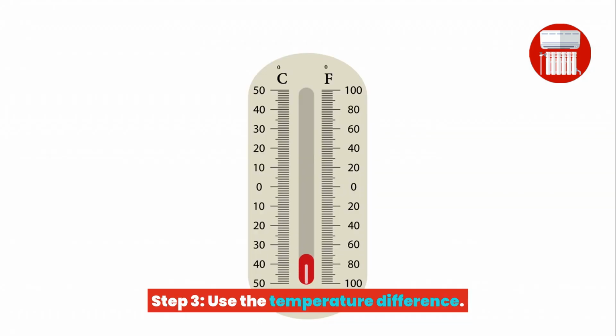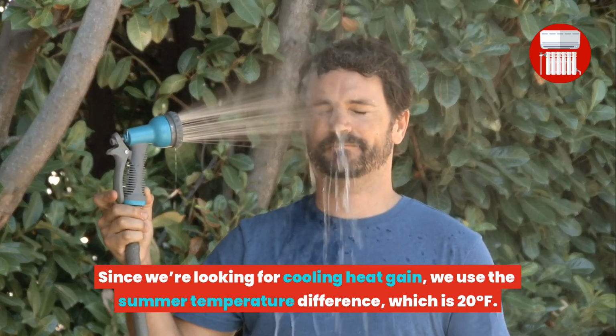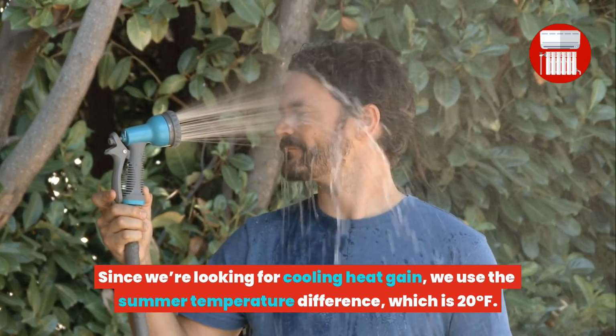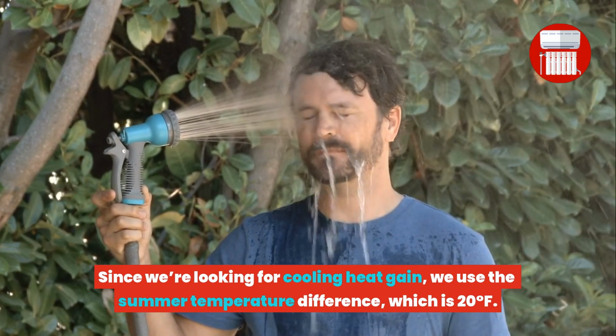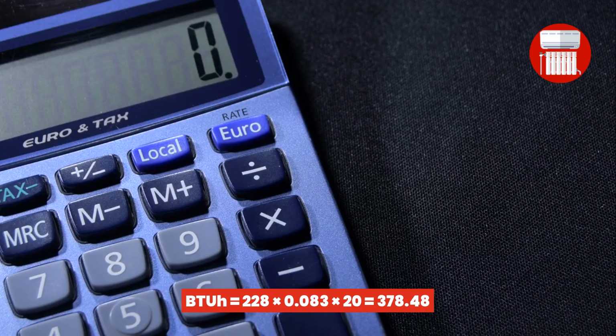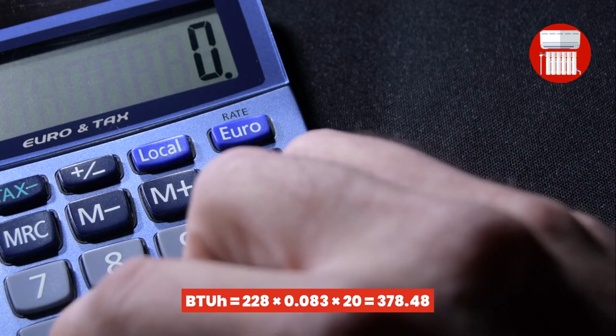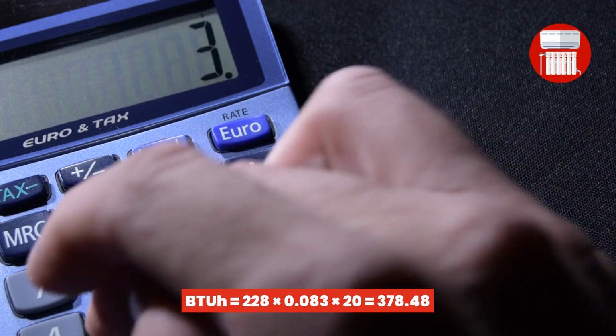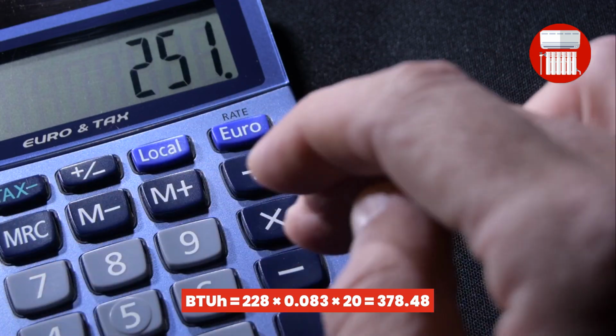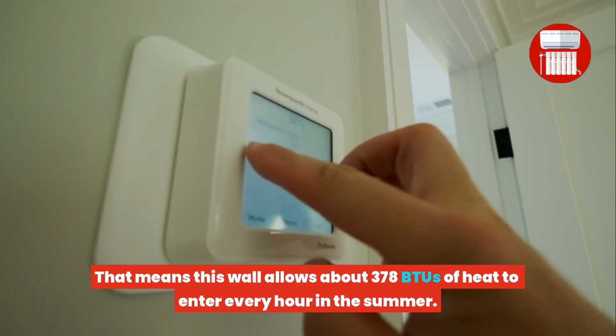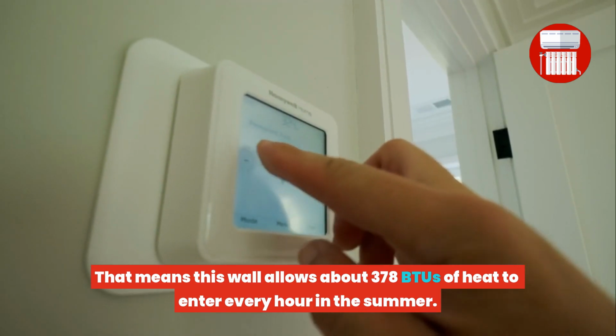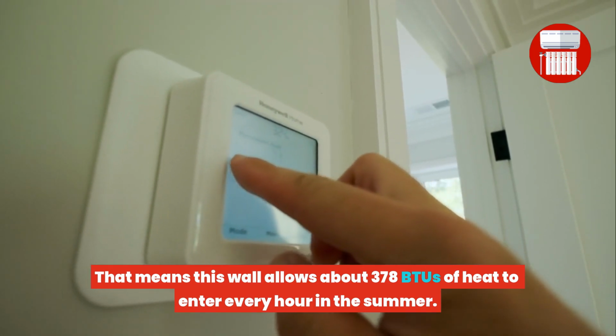Step 3, use the temperature difference. Since we're looking for cooling heat gain, we use the summer temperature difference, which is 20 degrees Fahrenheit. Now plug it in. BTUH equals 228 x 0.083 x 20 equals 378.48. That means this wall allows about 378 BTUs of heat to enter every hour in the summer.